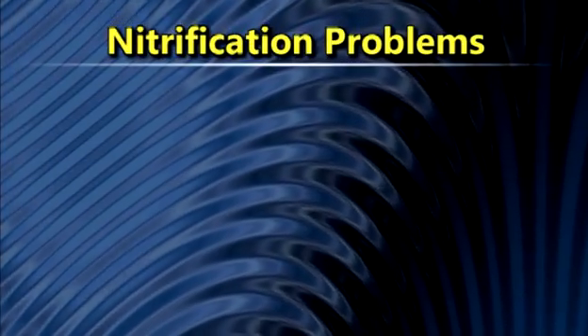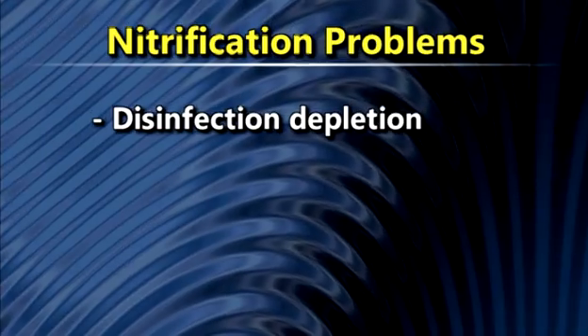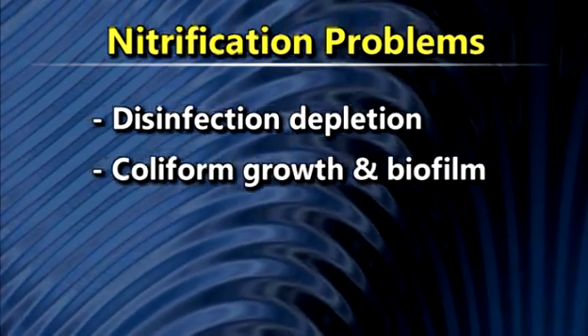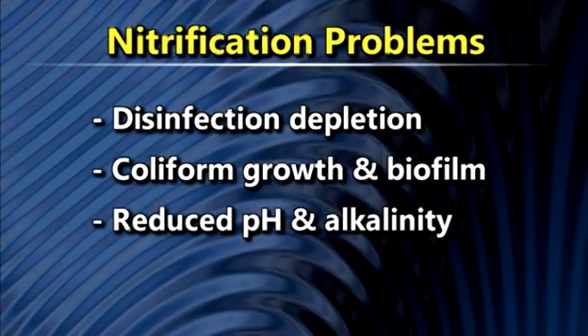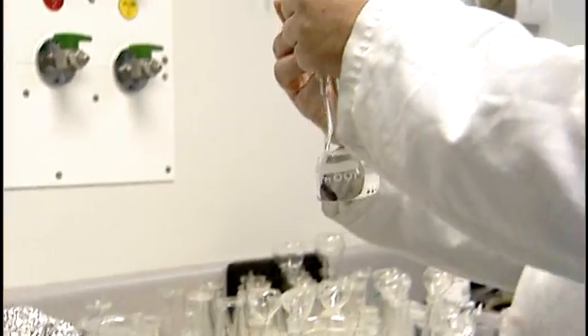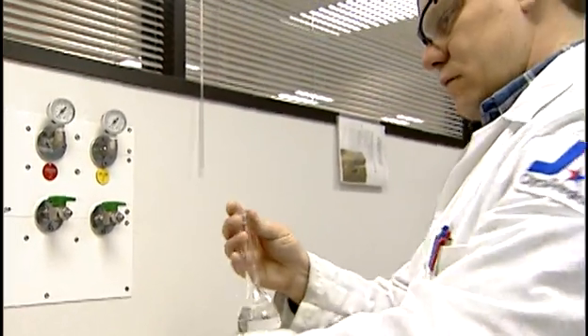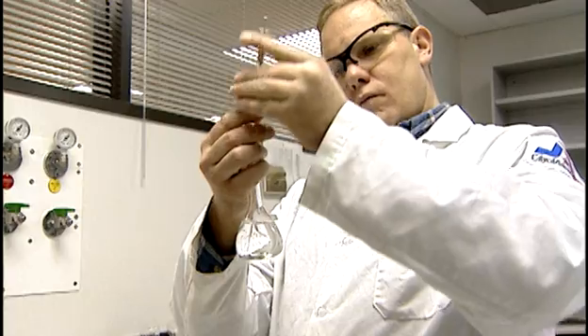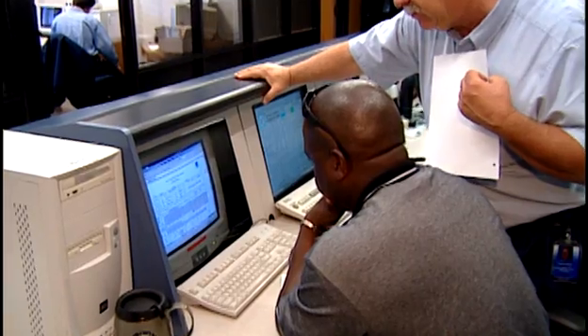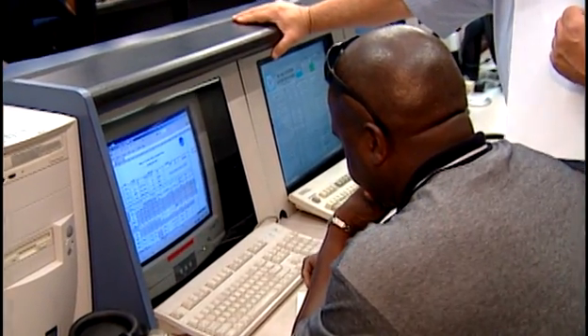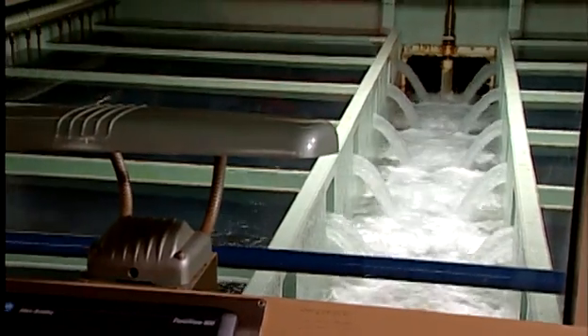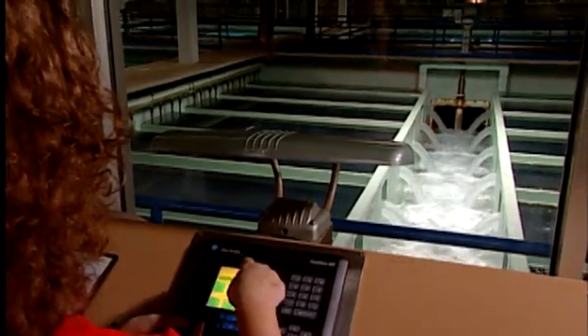Left unchecked, nitrification can lead to disinfection depletion, which can permit the growth of coliforms and other biofilm-related microorganisms, as well as reduced pH, alkalinity, and a decrease of dissolved oxygen. Controlling nitrification involves optimizing the chloramine treatment process and distribution system operation and maintenance to prevent occurrence. This is a difficult but not impossible balancing act for most water providers, and is required in order to meet nationally and regionally legislated regulations and requirements.